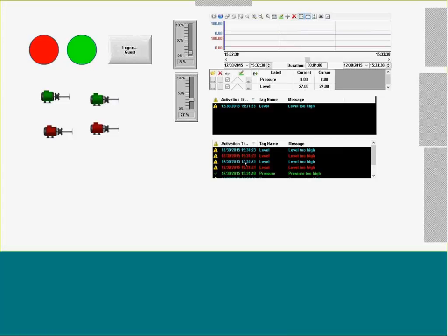So to sum up, if you just want to save the data, and the only reason to save the data is to visualize this data using the native objects from InduSoft and nothing else, the proprietary format, which is the default, would suffice. If you want to share this information with other systems, or if you want to generate dashboards and reports, retrieving, filtering, and calculating data based on the history points, the database would be a better option. Hopefully it answers your question.